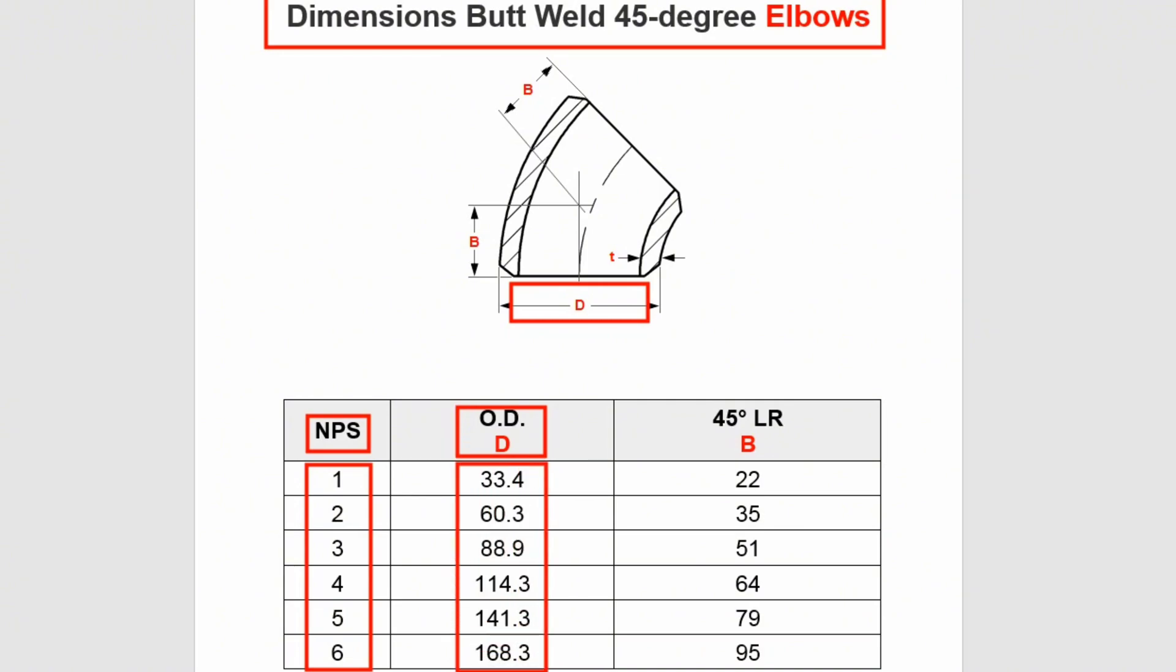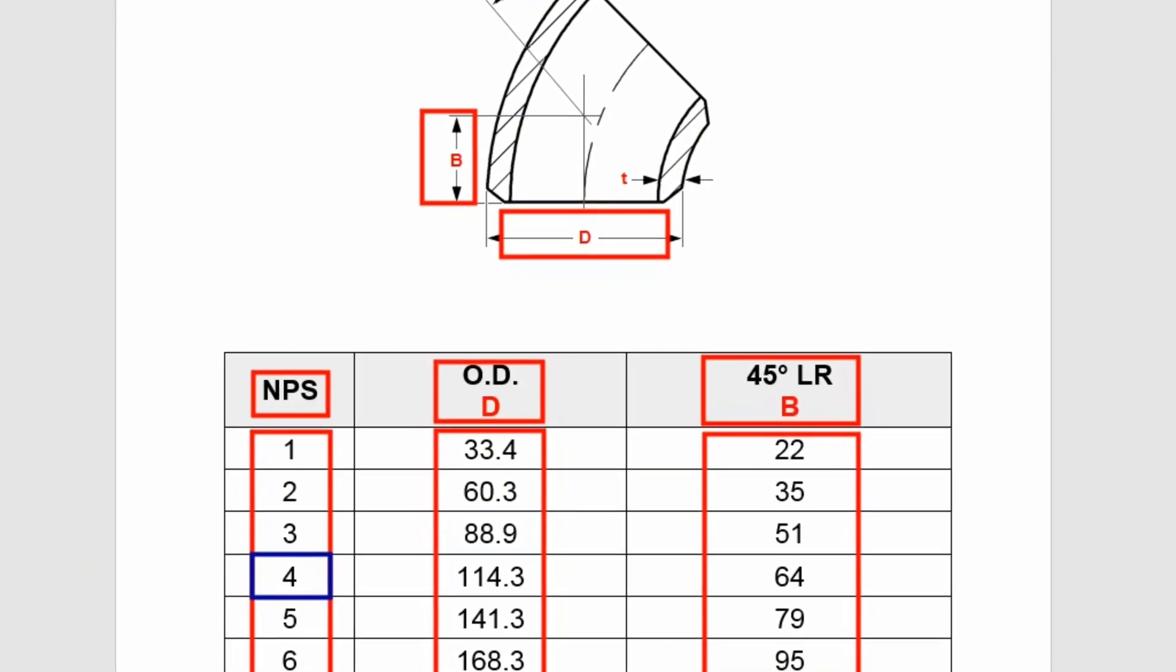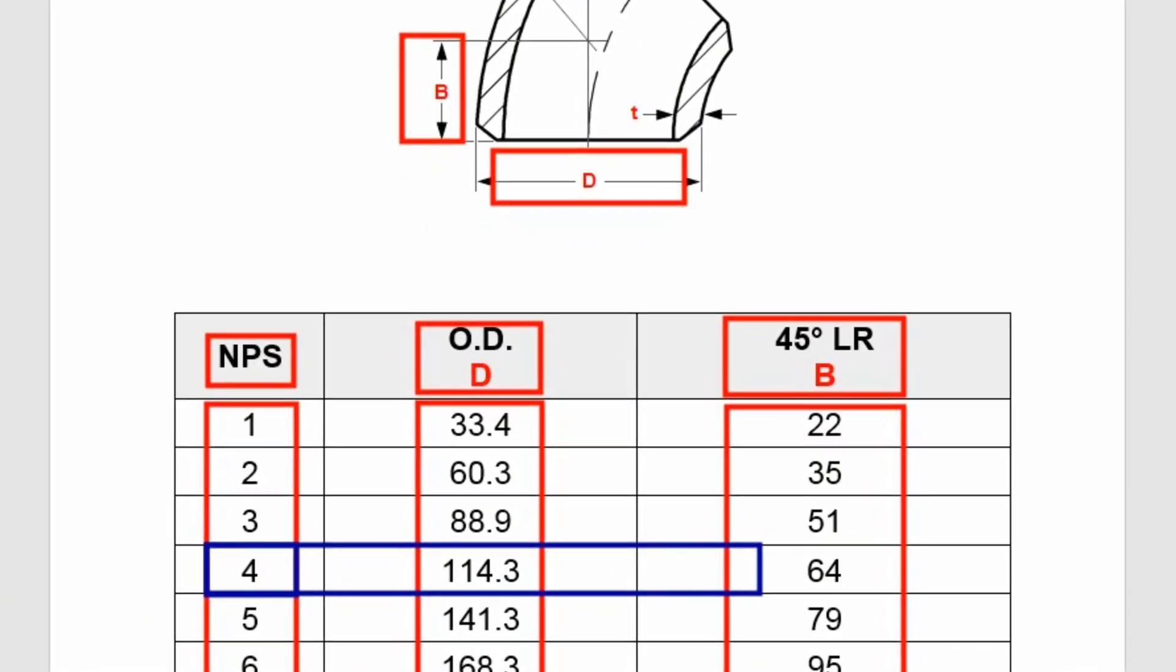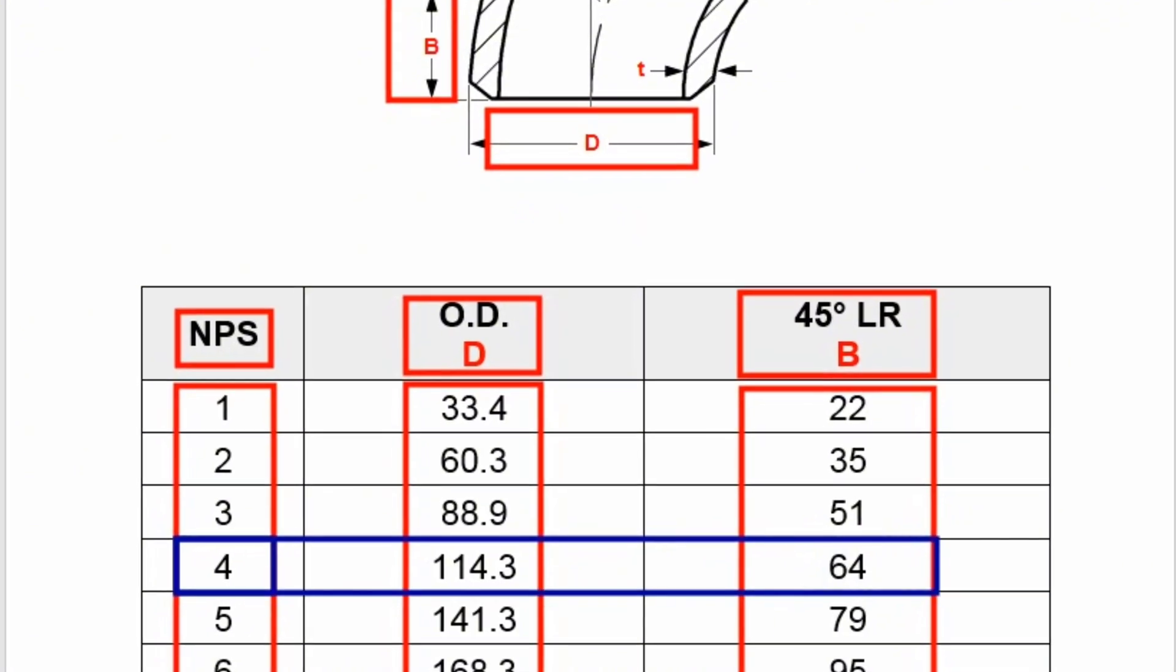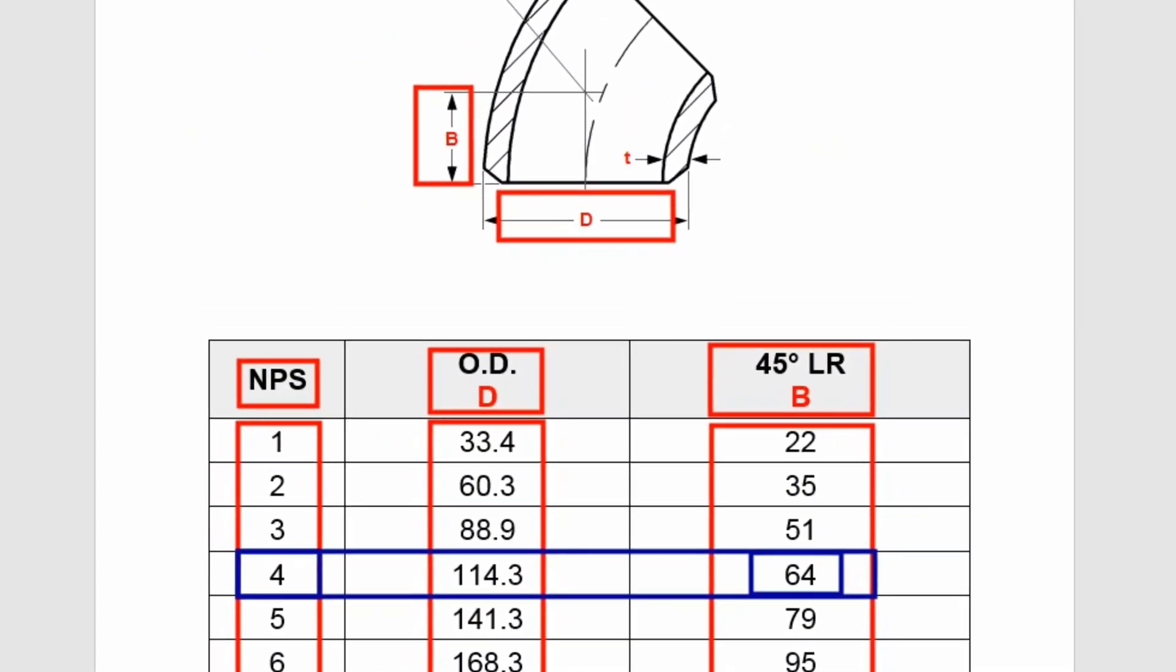B is the center to end of the 45-degree long radius butt weld elbow and shows in this column. We will look to this row: nominal pipe size is 4-inch, outside diameter is 114.3 millimeters, and the center to end of the 45-degree butt weld long radius elbow length is 64 millimeters.